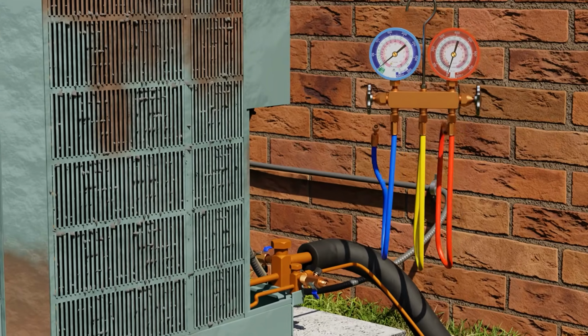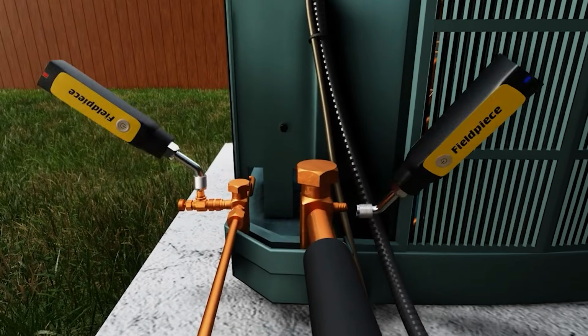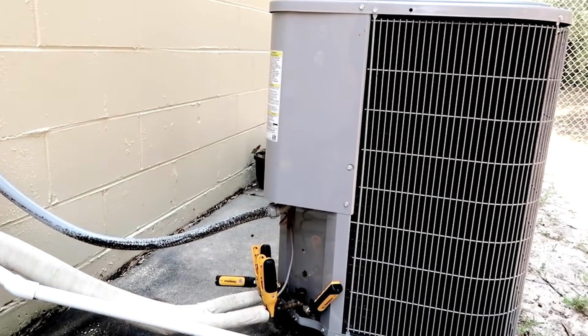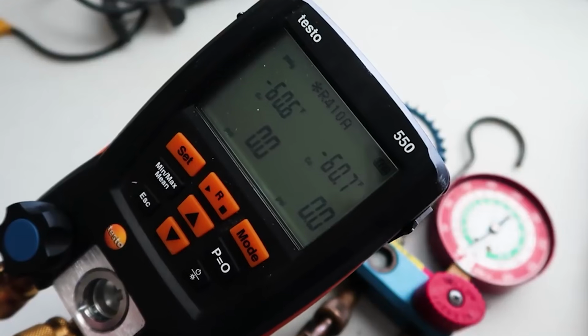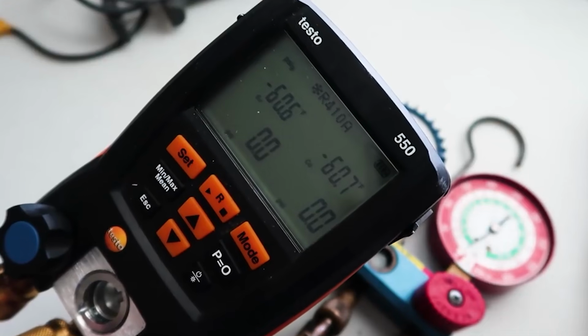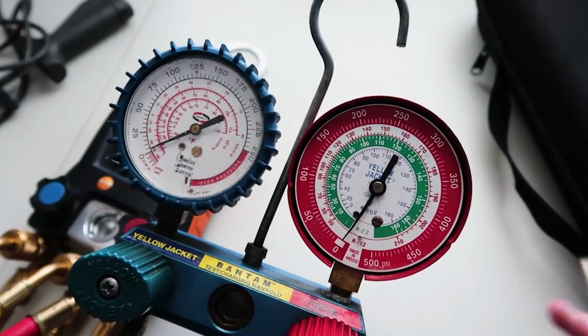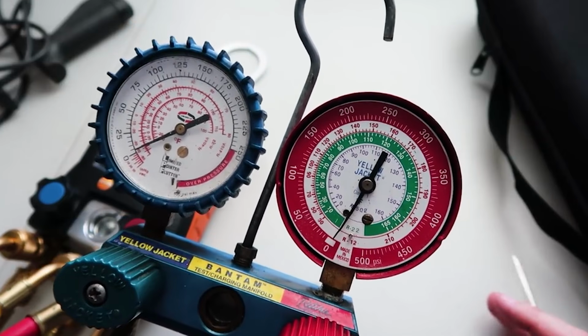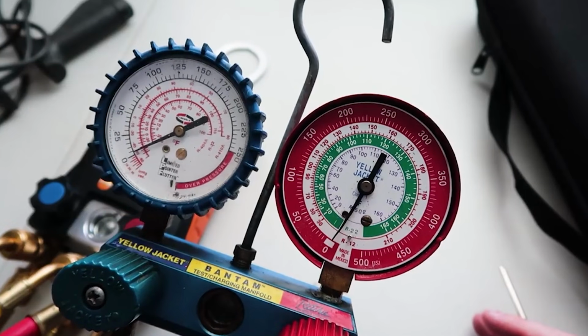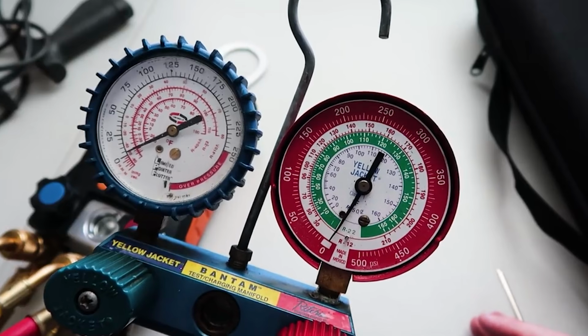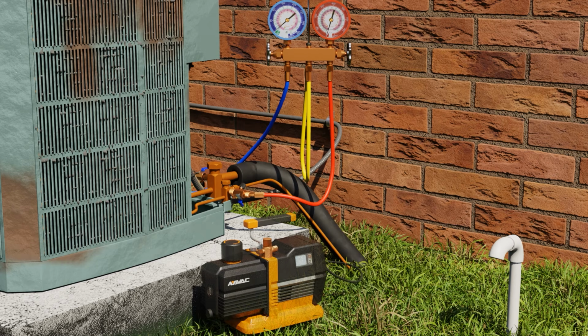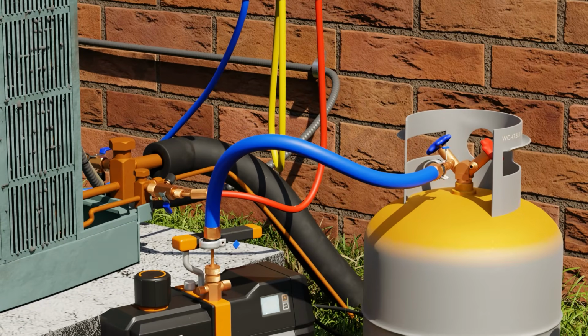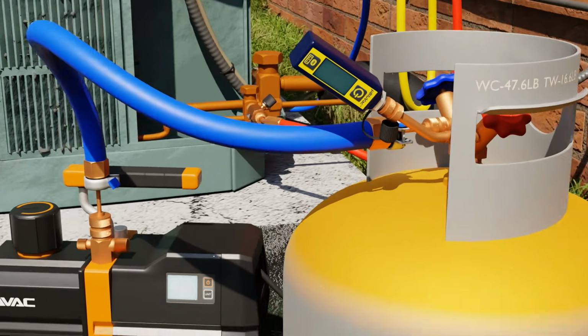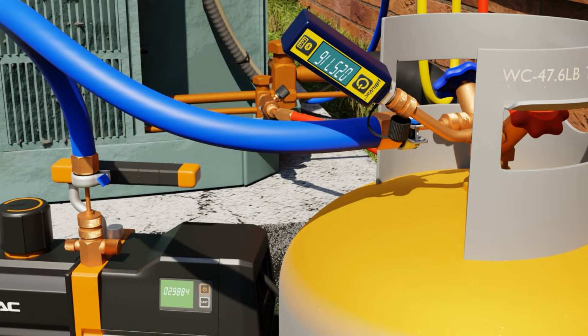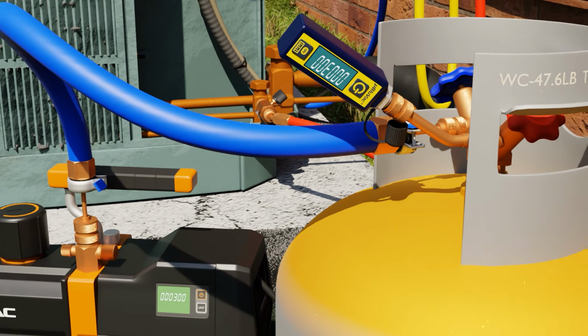Here I'm showing the use of an analog manifold set. You could also use a set of probes and hoses to do this, or use a digital manifold. For recovery, I prefer using a simple analog manifold because it's always possible that the existing system has contaminated refrigerant or oil, so I'm less worried about contaminating my inexpensive analog gauge. If you're starting with a fresh recovery tank, you want to make sure to pull a vacuum on the tank before you recover refrigerant into the tank. That way there's no air or moisture in the tank.